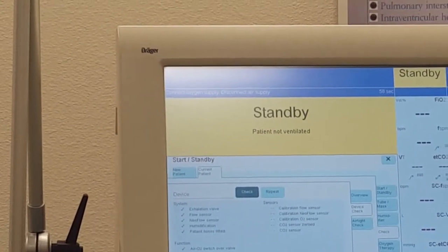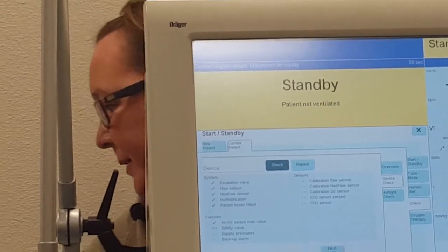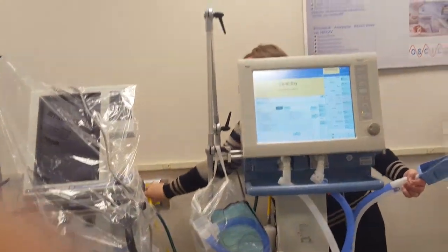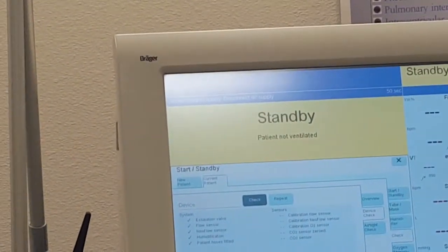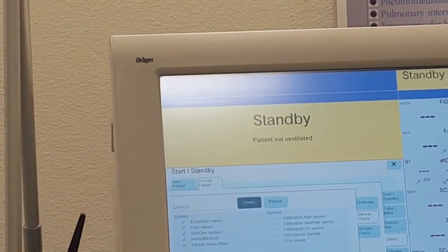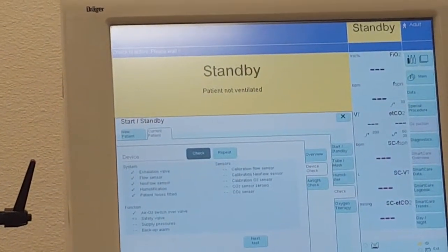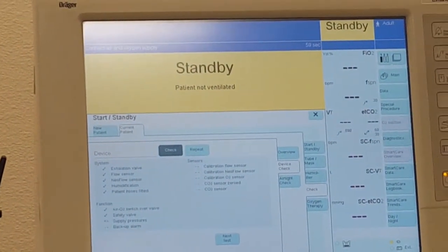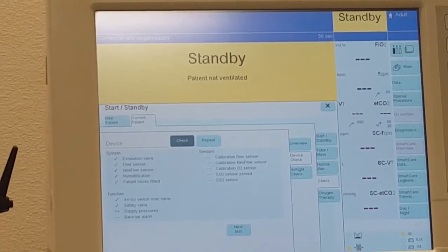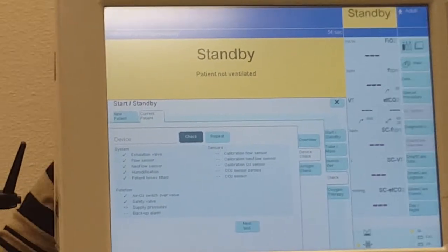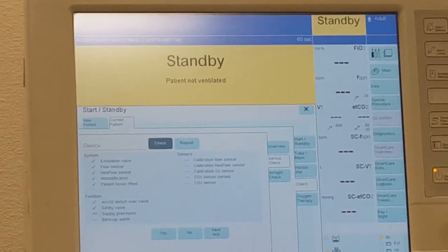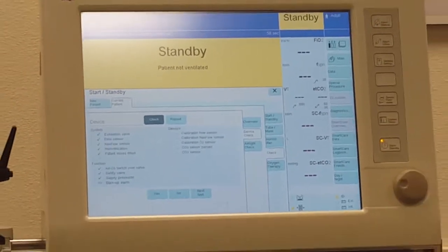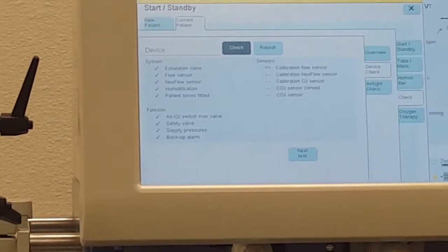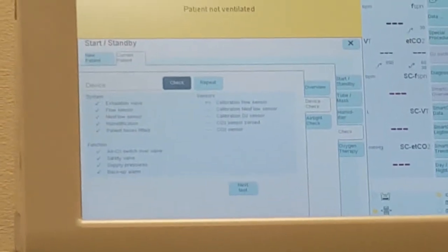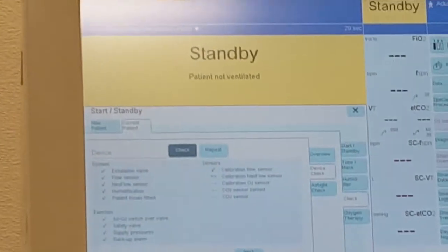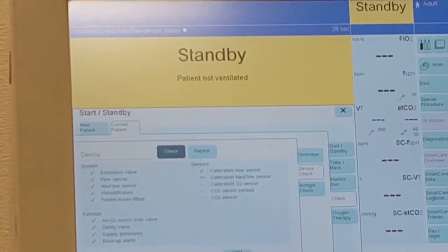Connect O2, disconnect air. We'll put this one back in. Then it should say check is active, please wait. It's also checking the safety valve. It told me to put my air back in, so I'm doing that. Checking that the alarm works, it does, so hit yes. And calibration okay, then it's doing the flow sensor.